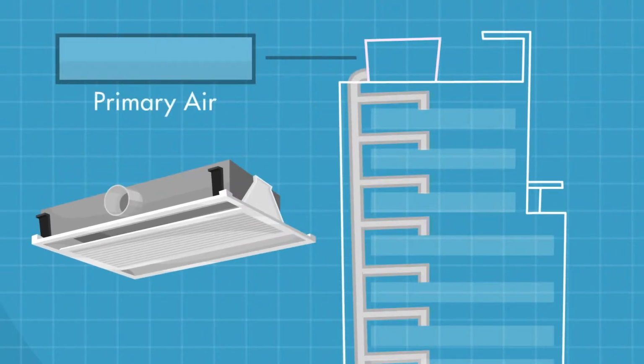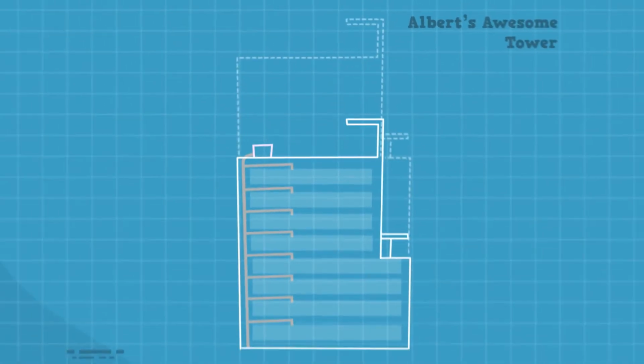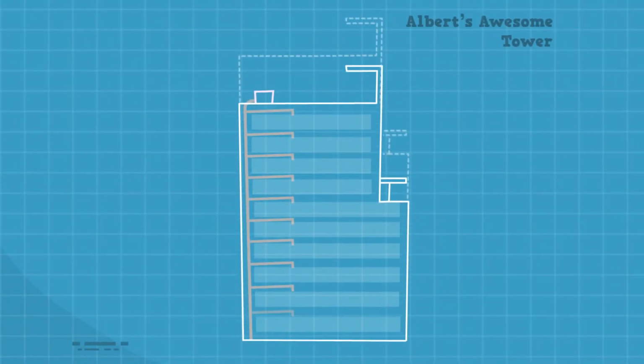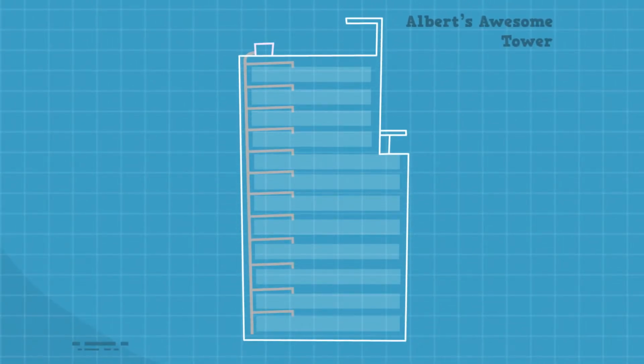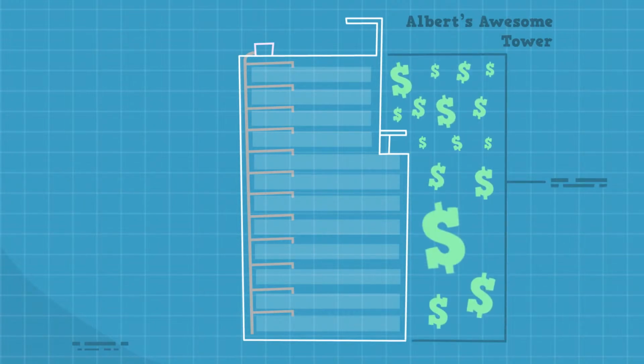Second, while active beams still require dehumidified air from the central plant, they require a lot less primary air, meaning lower fan power and smaller ductwork. This allowed Albert to fit more floors into his building spec. And more floors means more leasable office space.